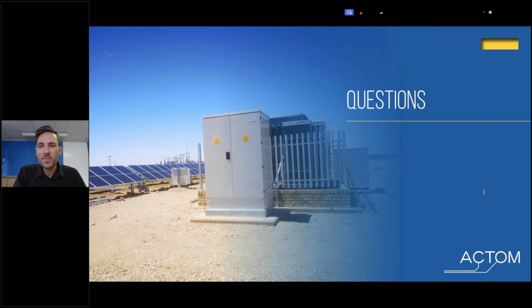Sai? Okay, so yes, we had to retrofit those sensors. We had a DGA on site, but we had to retrofit the pressure sensor as well as the temperature sensor. But with the new IPPs, we're actually giving a proposal or an option where you could fit it before the transformer leaves the factory. Sorry about the background noise. The other option is that we have it already designed so we don't have to make a plan on site in terms of how we attach the devices, so it's an option at a later stage too that you could fit the IoT devices. And if, for example, it's PTK specifically, which is a much smaller transformer, then we don't go to the 9 gas, because the 9 gas DGAs are quite expensive. Hence, I think Wesley mentioned we are looking at options of 2 gases as well that will do the same function for the PTKs.